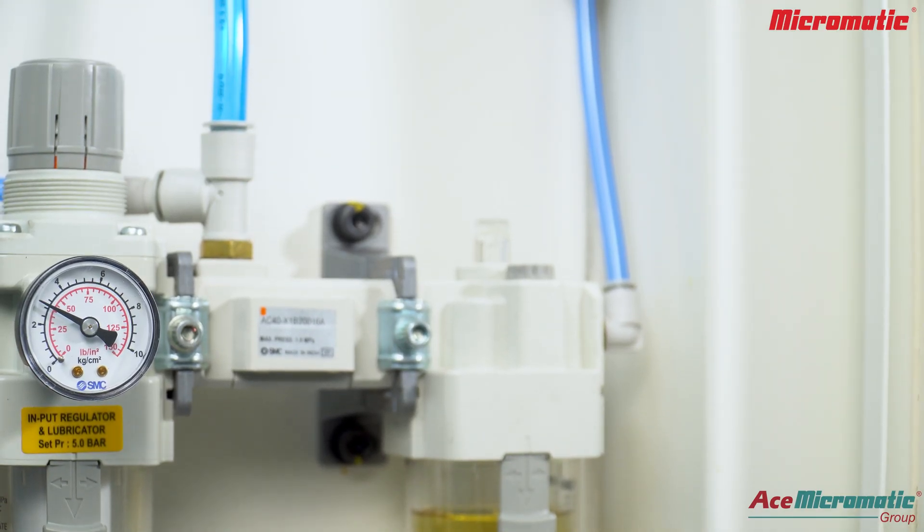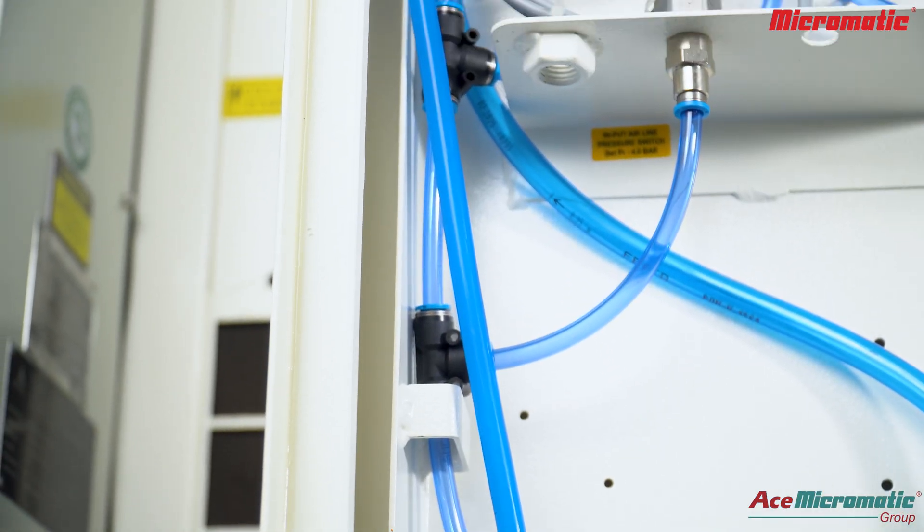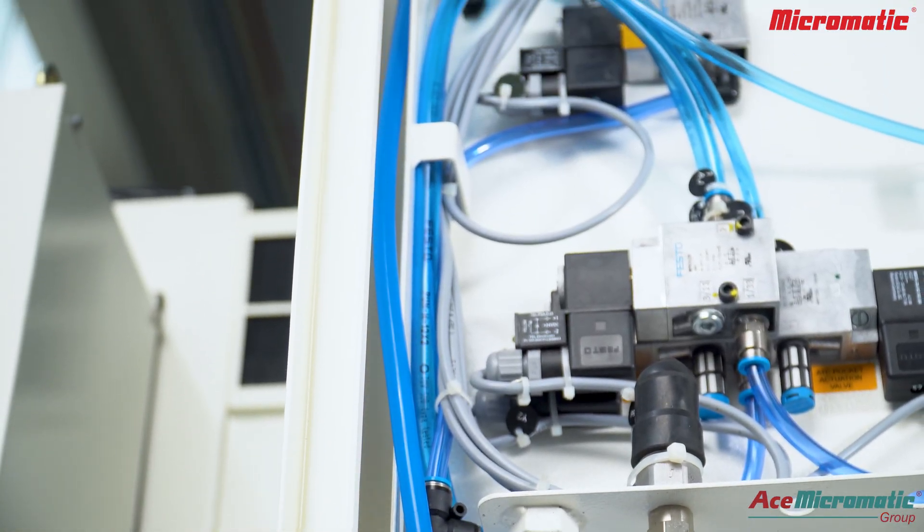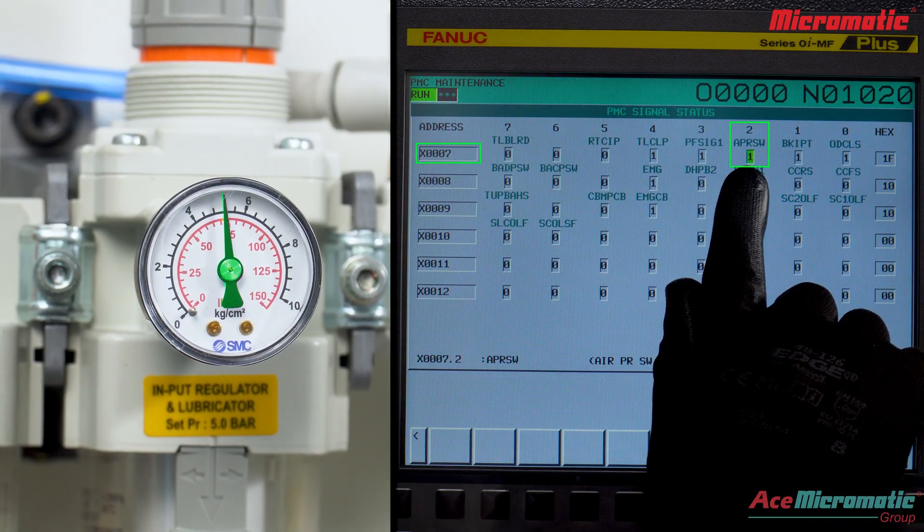Check hose connections and any leakage in the incoming line. Now you can see pressure is restored and X7.2 becomes 1.